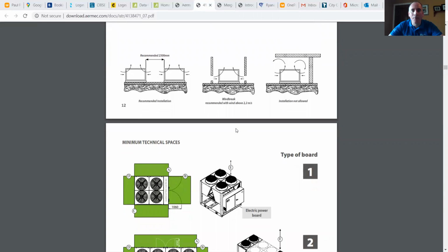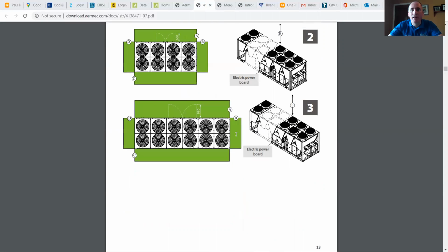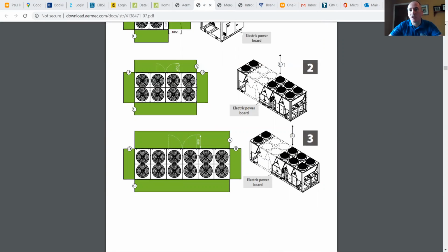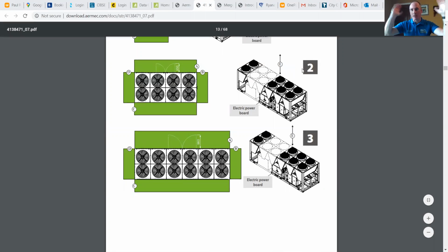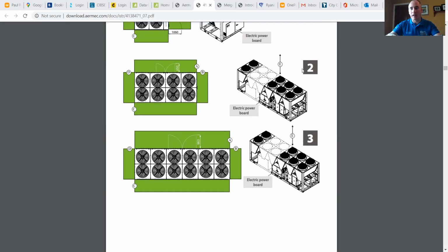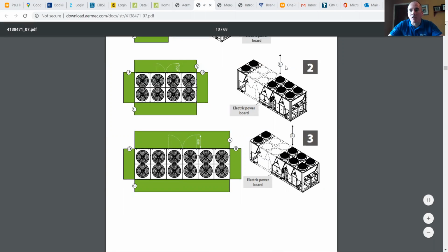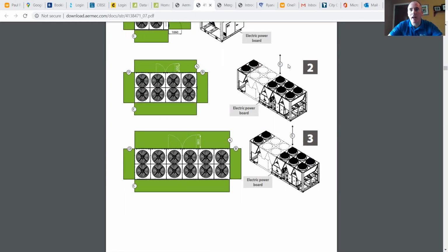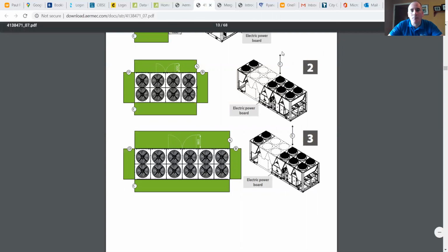By the way, if you have, let's say, a grill over the chiller, so let's say the chiller is in the plant room area, but you have an open area above it, very often with like a grate. Obviously, you need to be aware that the grate could reduce your airflow, sometimes up as much as 50% perhaps. So you need to tell us if that's the situation, and we can compensate for that reduction in space, because that's really what you're doing. You're reducing the space for the airflow, but we can counteract that with high static pressure fans, or even centrifugal fans for ducting if needs be. So just so as you're aware of all that.